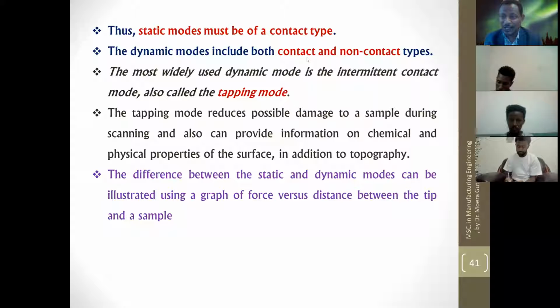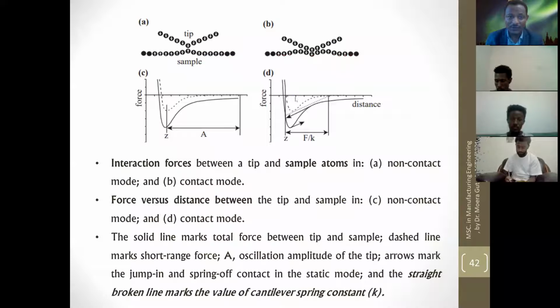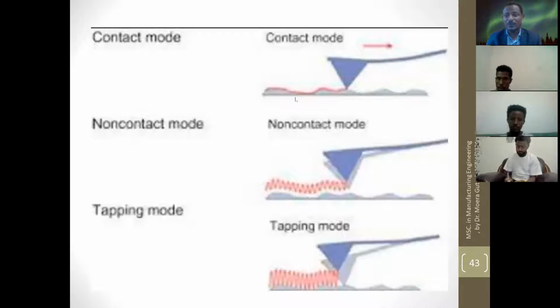There are three things. Dynamic, which measures oscillation, it can be contact, intermittent contact, or it can be non-contact. The intermittent contact one is typically called tapping mode. We will see that one. Okay. The dynamic mode can work in three of these. It can work in contact mode. It can work, the probe can touch intermittently the sample surface, or it cannot totally touch also, non-contact mode.